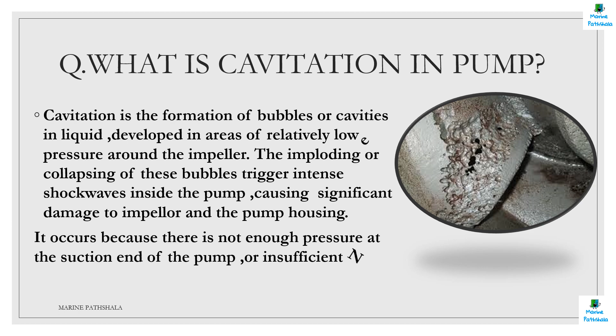What is cavitation in pump? Cavitation is a very common problem in the pumps. Cavitation is the formation of bubbles or cavities in a liquid developed in an area of relatively low pressure around the impeller. The imploding or collapsing of these bubbles trigger intense shock waves inside the pumps, causing significant damage to the impeller and pump housing. It occurs because there is not enough pressure at the suction end of the pump or insufficient net positive suction head available.